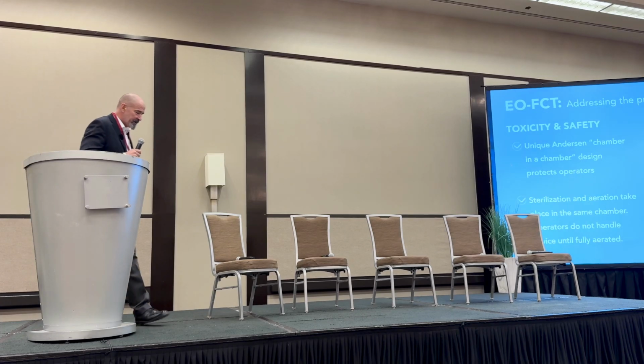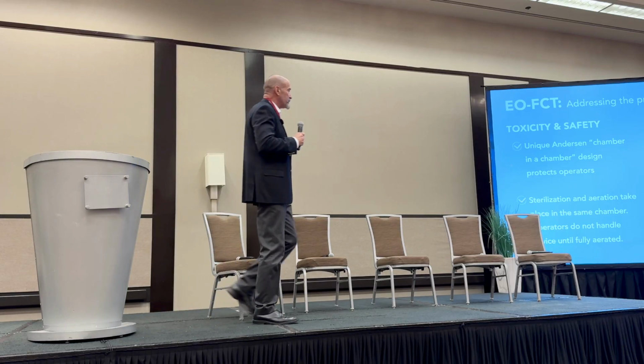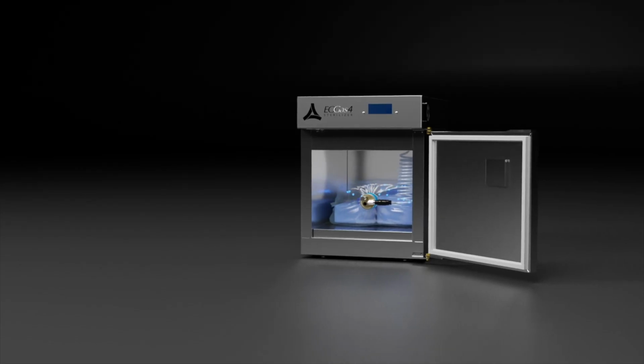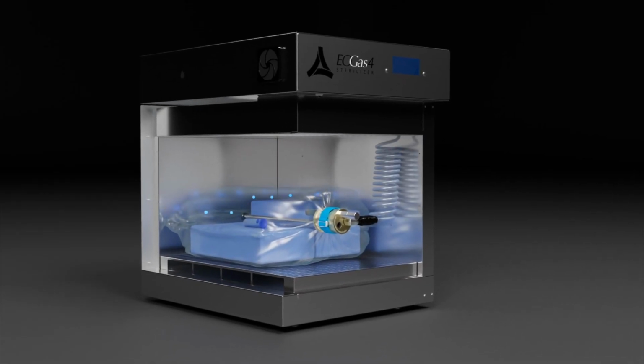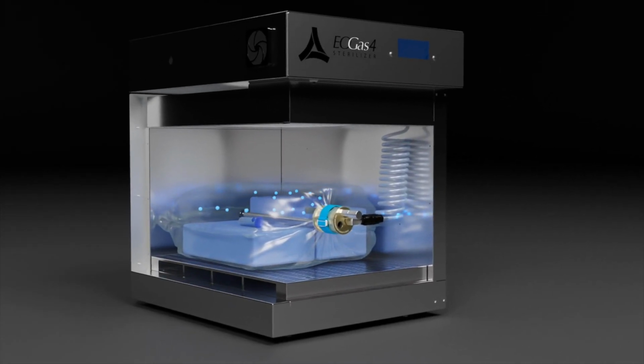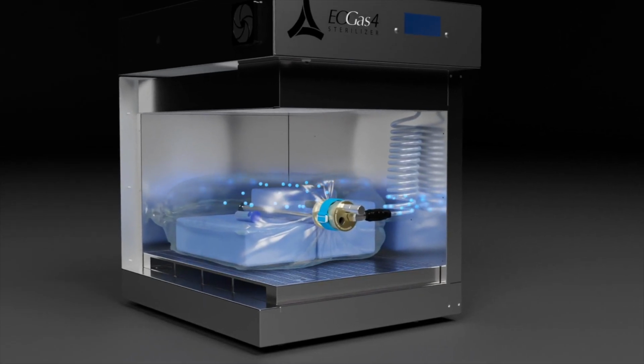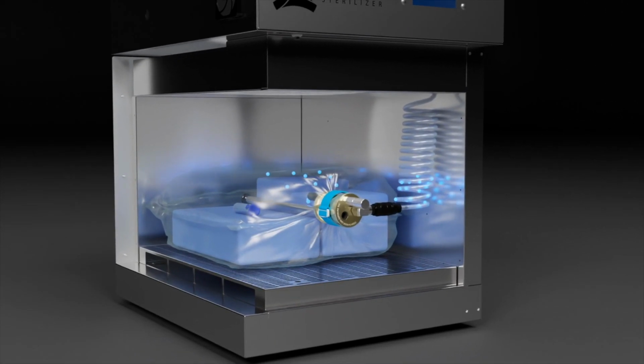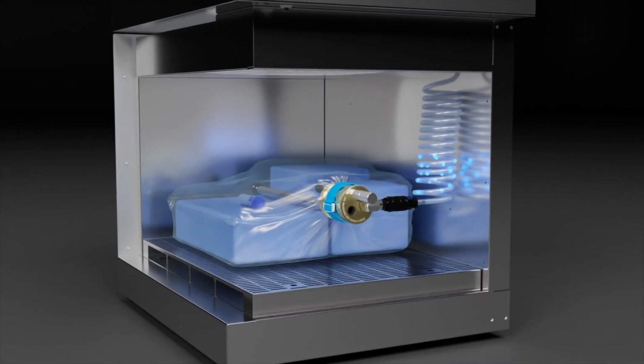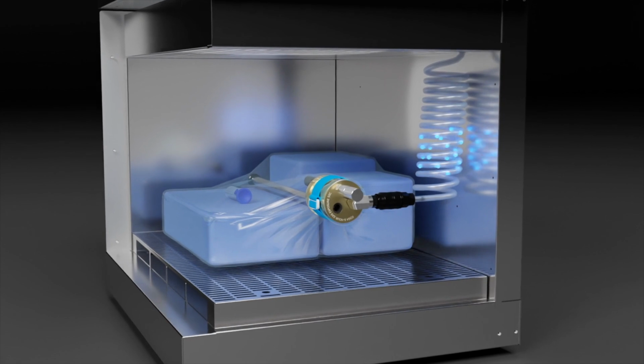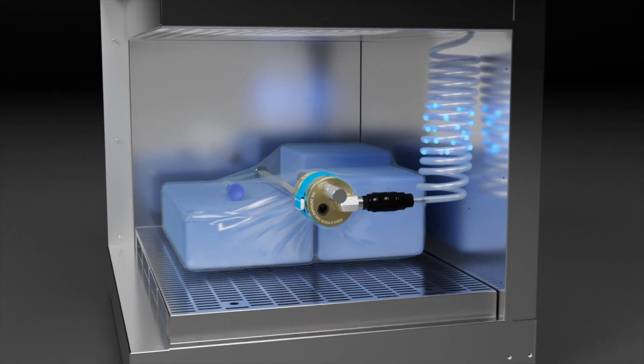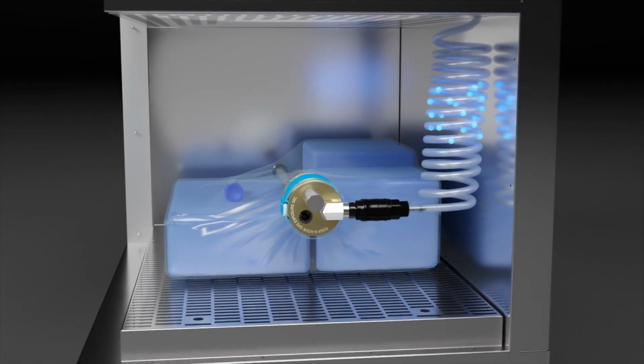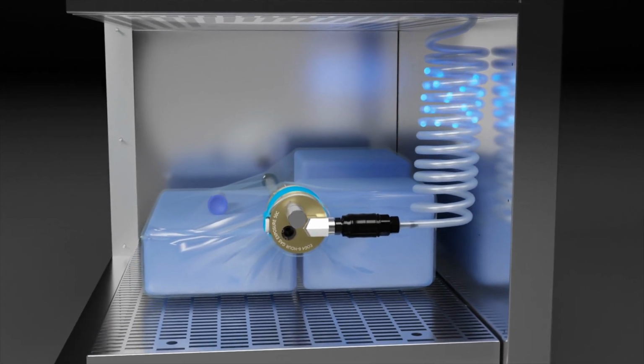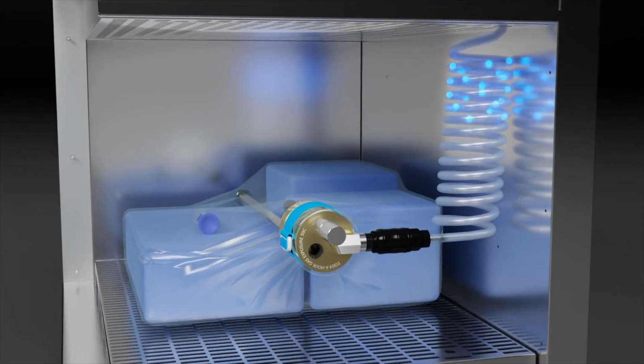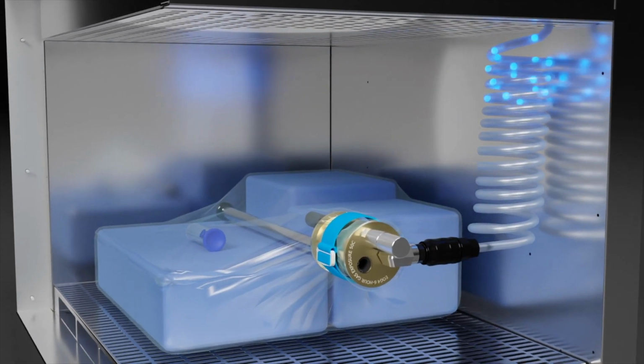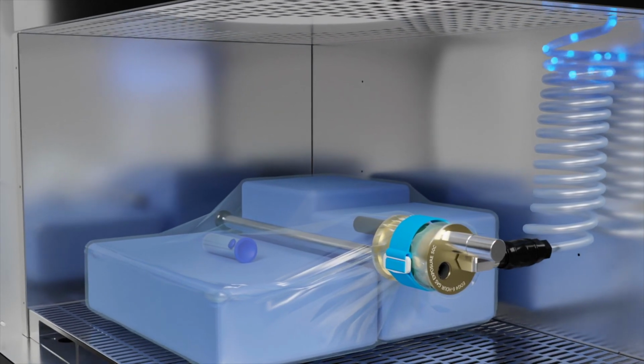So how do we do it? The key to the flexible chamber system is the flexible chamber. It's a sterilization bag, and the sterilization bag is loaded with the items that you're going to sterilize. It's sealed around a purge device, and at the start of the cycle, the purge device removes the air from the bag. The bag, which is the chamber, collapses around the items that you're sterilizing. You can think of a vacuum-sealed bag of coffee, the way that the packaging really contorts around the product. Well, it's the same thing here.